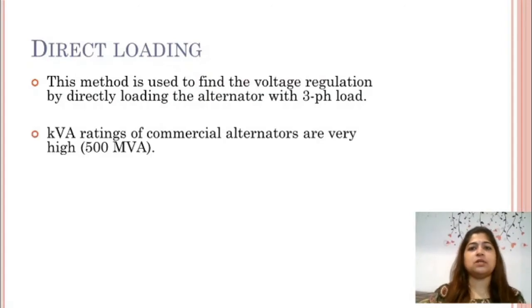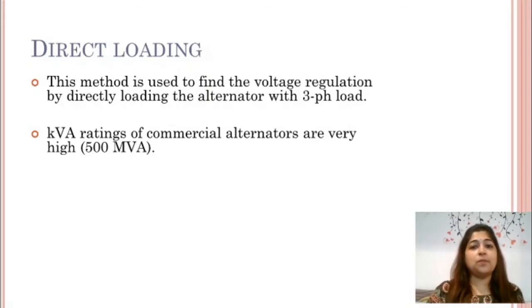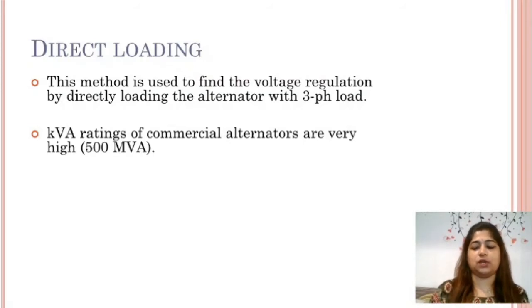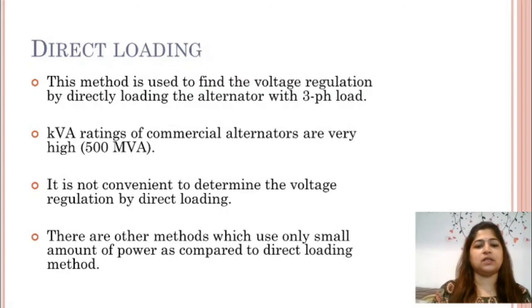Direct loading is a method in which we directly load the alternator with the load and then find out the regulation by measuring the terminal voltage. But this method is used only when you have small loads. When we talk about bigger alternators like commercial alternators which range up to 500 MVA, it is impossible to physically load the alternator by that much load to find out the voltage regulation. So for such alternators there are other methods.